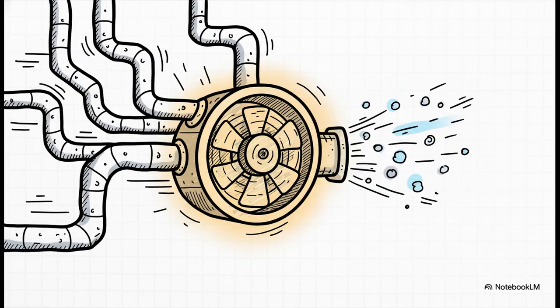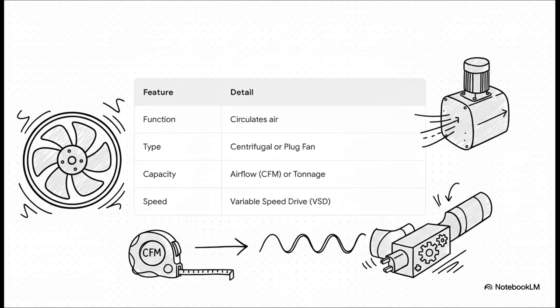First up, you've got the fan. Look, if the AHU is the lungs, then the fan is the heart. It's the muscle that pumps air through the whole system, pushing it through the filters, pulling it across the coils, and sending it out into this huge network of ducts to reach every single corner of the building. And we're not talking about just any old fan you'd buy at the hardware store. Engineers get really specific, choosing types like centrifugal or plug fans. Their capacity is measured in cubic feet per minute, or CFM.